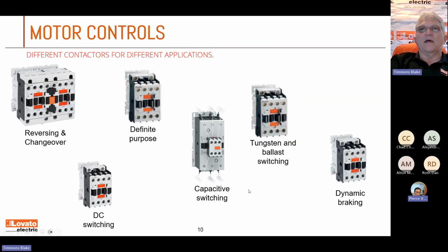Hey, Blake, that capacitive switching product is very interesting. There's one of those in every standard voltage source VFD. Does Lovato supply those to the VFD manufacturers? I don't know that we do, that I'm aware of. They do a lot of stuff they don't always tell me. It might be an OEM thing, but that's exactly what you do to slow charge the cap bank on a standard VFD. You bring resistors in first for a few milliseconds, and then you short them out with a main contactor. Yeah. Good.